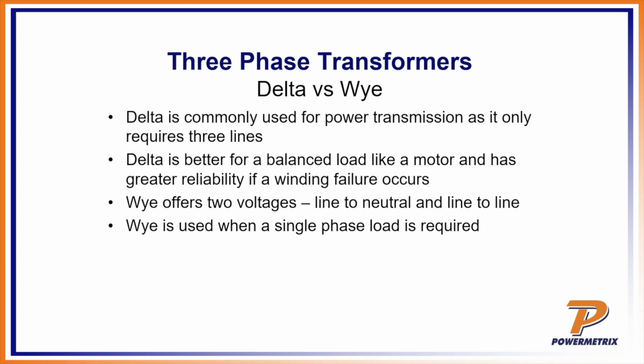Now the Y offers 2 voltages, as you can see there. It says line to neutral and line to line. So the Y is used when a single phase load is required. And the Y is more popular, a lot simpler to wire up. Everything seems more clear. And I know from you and I testing, I'd much rather test the Y sides than the delta sides. But the delta has its advantages, and you can see there why.